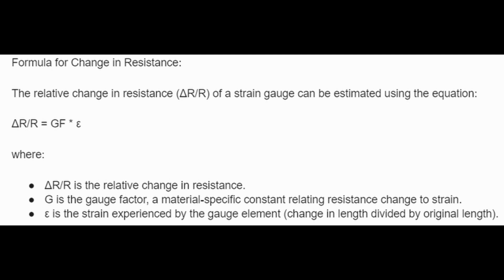Formula for change in resistance. The relative change in resistance, delta R over R, of a strain gauge can be estimated using the equation delta R over R equals GF times epsilon. Delta R over R is the relative change in resistance. GF is the gauge factor, a material-specific constant relating resistance change to strain, and epsilon is the strain experienced by the gauge element: change in length divided by original length.